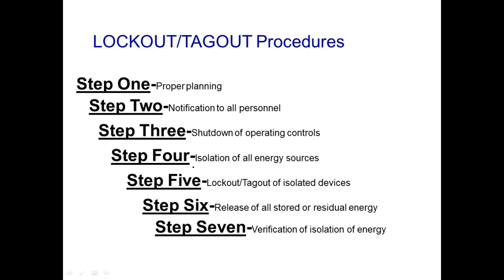Shutdown of operational controls. You need to understand how to properly shut down a system. You can't just go out there and kill power, because you have to park things—put things down where they're not going to collapse. You might have to override a lift and lower it down so it don't fall when you cut off the pneumatic pressure.